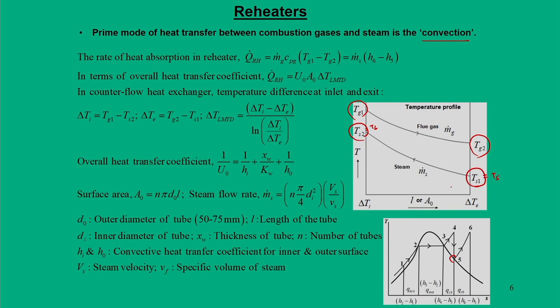We have two temperature differences: delta T_i = T_g1 minus T_s2, and delta T_e = T_g2 minus T_s1. From these temperature differentials one can define the logarithmic mean temperature difference (LMTD). Once the LMTD is found, we link heat transfer through the expression involving overall heat transfer coefficient, outer surface area, and delta T_LMTD. Since heat transfer occurs through convection, we can write a heat balance equation: heat rejected by flue gas equals heat added to the steam.